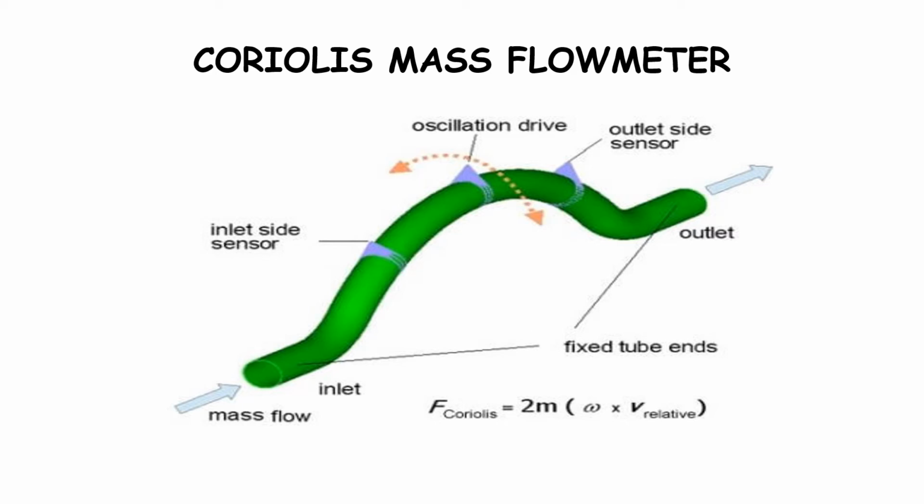The main feature of this Coriolis meter is that it can be applied for a variety of applications ranging from adhesives and coating to liquid nitrogen. The rangeability of the curved tube design may vary from 100:1 to 200:1, whereas for straight tube meters, its range is limited to about 30:1 to 50:1. Besides, the accuracy of the straight tube meters is low.